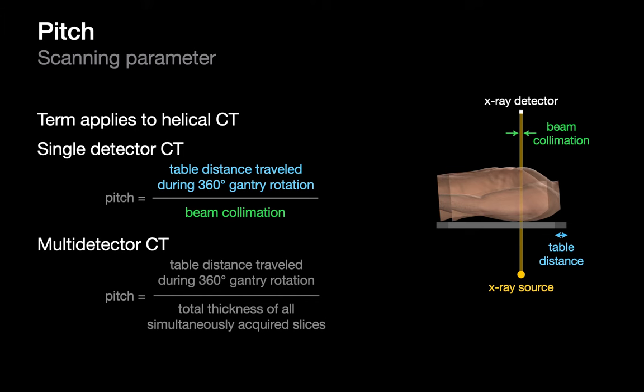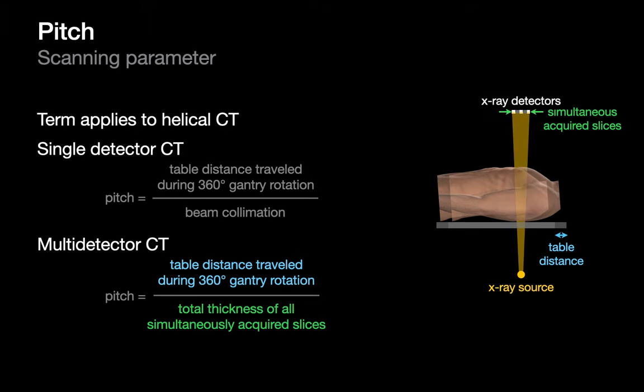Pitch is a term used with helical acquisition CTs that describes how tight that spiral is. For a single-detector CT, pitch is the distance the table travels during one gantry rotation divided by the thickness of the x-ray beam. For multi-detector CTs, pitch is defined as the distance the table travels during one gantry rotation divided by the total thickness of all slices acquired simultaneously by one rotation.